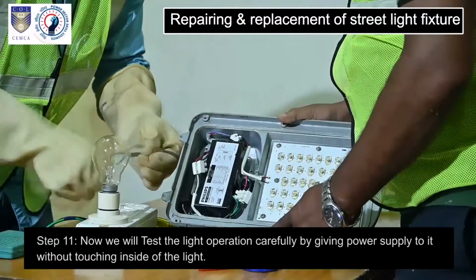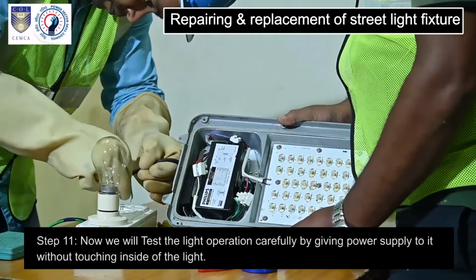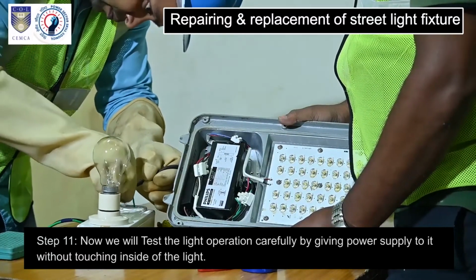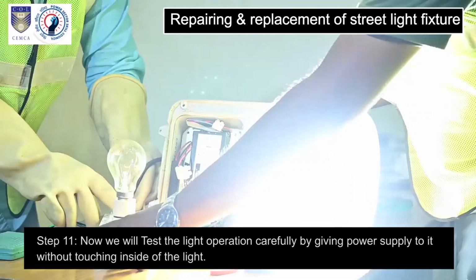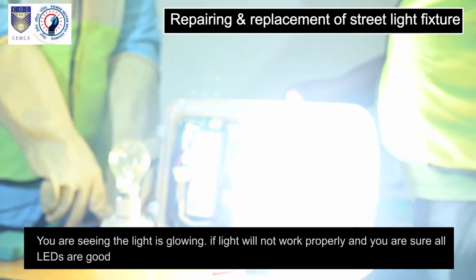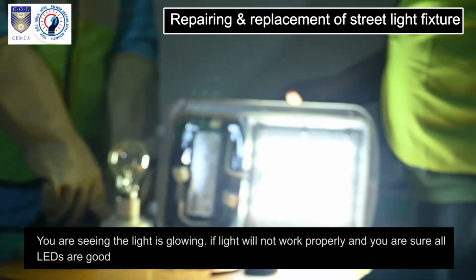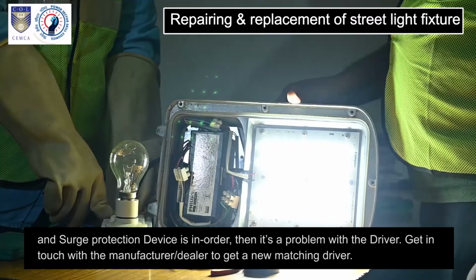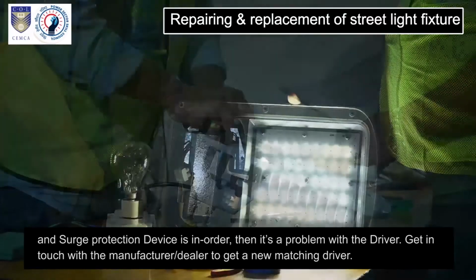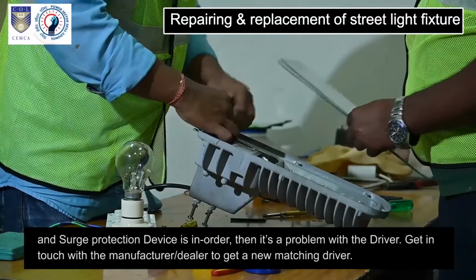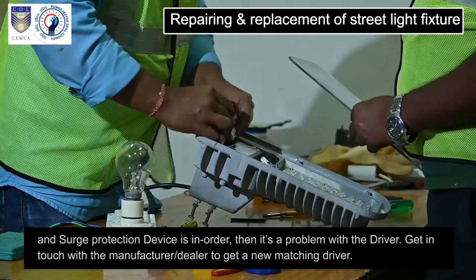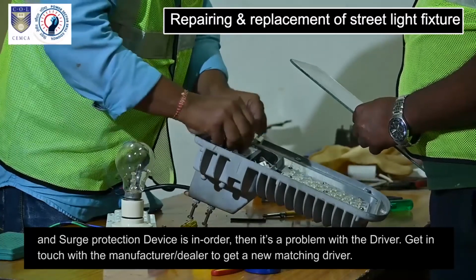Step 11. Now we will test the light operation carefully by giving power supply to it without touching the inside of the light. You are seeing the light is glowing. If the light does not work properly and you're sure all LEDs are good and the surge protection device is in order, then it's a problem with the driver. Get in touch with the manufacturer or dealer to get a new matching driver.